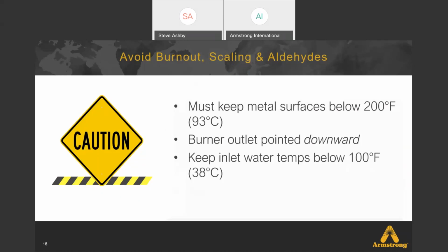And we must keep inlet temperatures below 100 degrees. Again, that is to prevent scaling issues in the internals of the heater itself. And lastly, but not leastly, recirculation back to the heater is not recommended. Now, with that said, there are applications where recirculation is allowed and works very well.